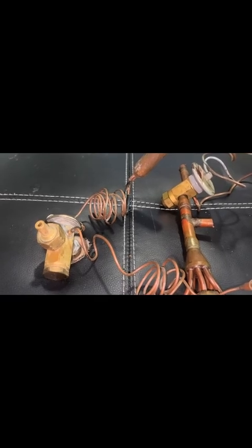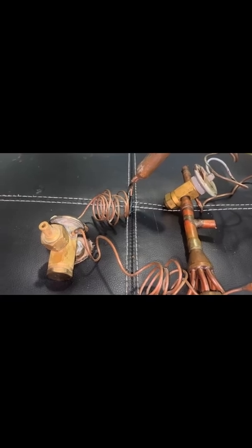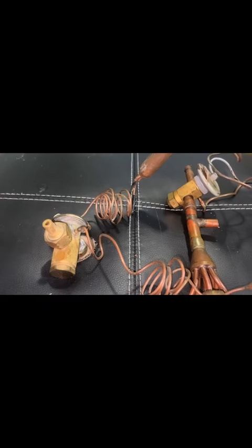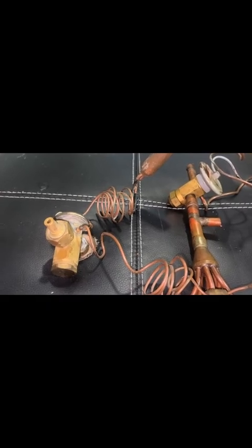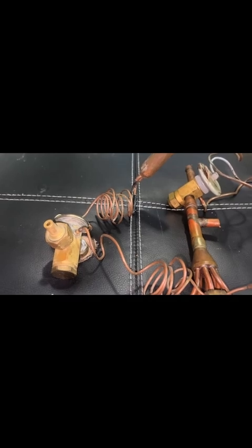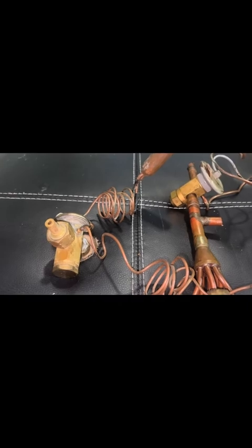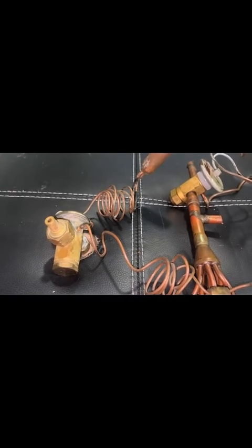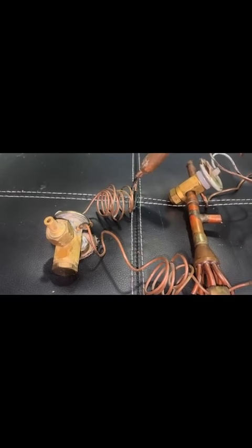But for your heat pump systems, TXVs for heat pumps must have an internal or external check valve to allow for the reverse flow of refrigerant during the heating cycle, bypassing the metering mechanism when flow is in the reverse direction. Without this check valve bypass, a standard AC only TXV would not work in a heat pump application.